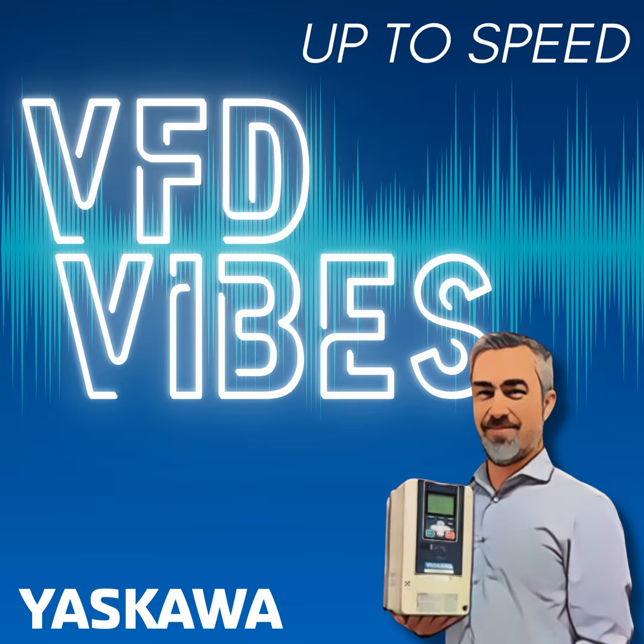Okay. So now my phase to ground voltage goes from 277 to 480. Now, it's appropriate here to talk a little bit about common mode, or what they call zero sequence voltages. This common mode voltage, if you can imagine, is the algebraic sum of the three-phase voltages to ground at any given time. So this is like VA plus VB plus VC, that voltage with respect to ground, the average of the three voltages.